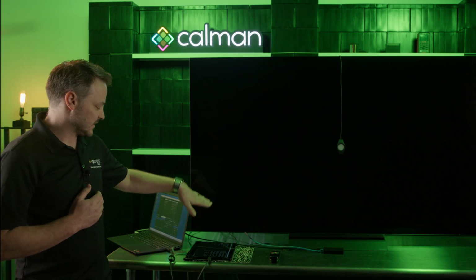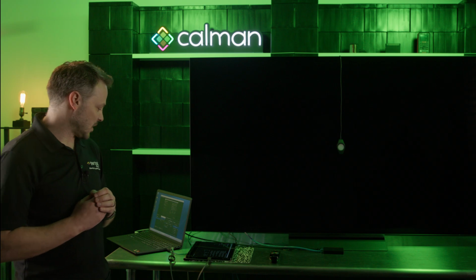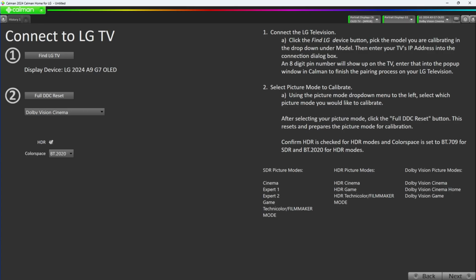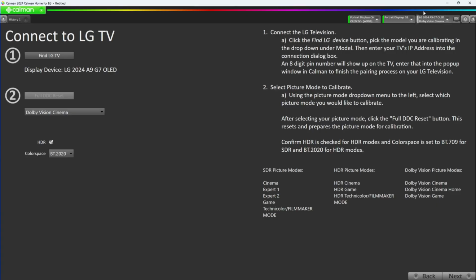Next, we are going to make sure that HDR and BT 2020 checkbox settings are set correctly. They should be set already for you. And we're going to run the full DDC reset before we continue on with the calibration. Running that full DDC reset just makes sure that we are in a good state to start the calibration. And just like before, as that reset happens, you'll notice that there is pulsing on the display tab in the top right. As soon as that's done, we'll know that the full reset has finished.